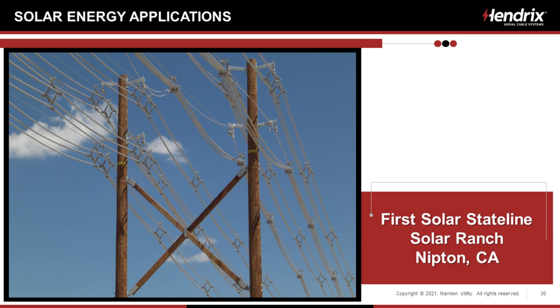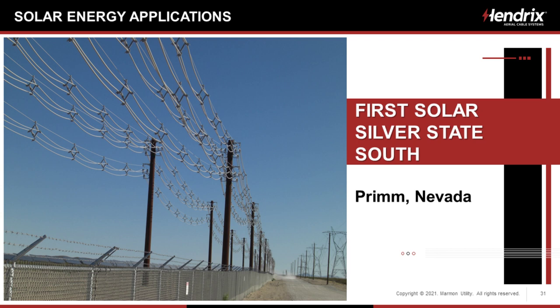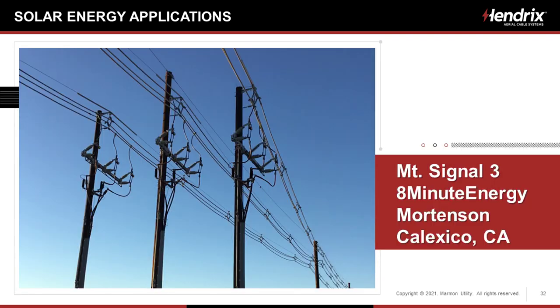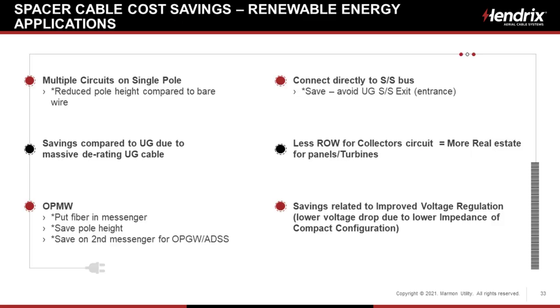Here's First Solar State Line. That's on the state line between Nevada and California. This is during construction. So we had 8 circuits in that facility. And then right across the street from State Line is First Solar Silver State South, and that's in Primm, Nevada, even though it's precisely right on the state line. So those are some real fun jobs that we did that are still cooking away after a decade or more. It's a project we did with, the owner was 8 Minute Energy, Mortenson was the EPC, Mount Signal 3. I forget how many collectors we had on there, but we ran one pole line into the sub.